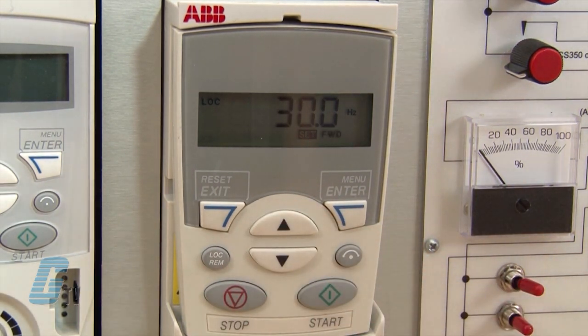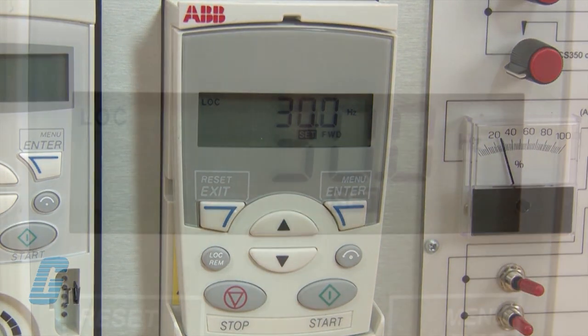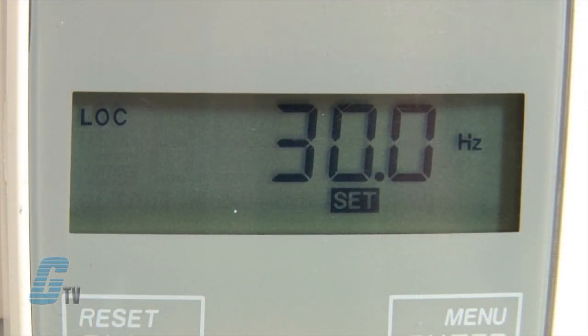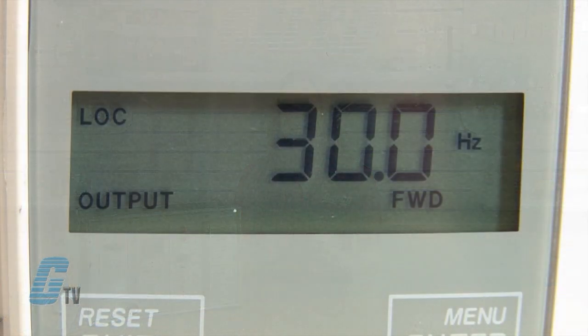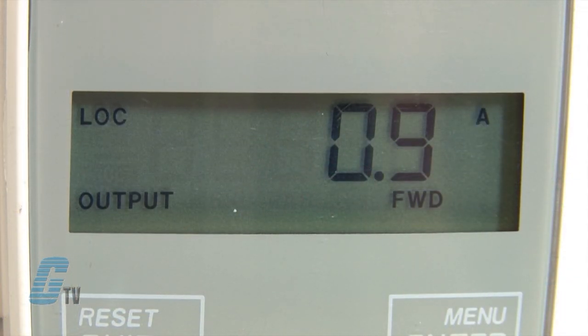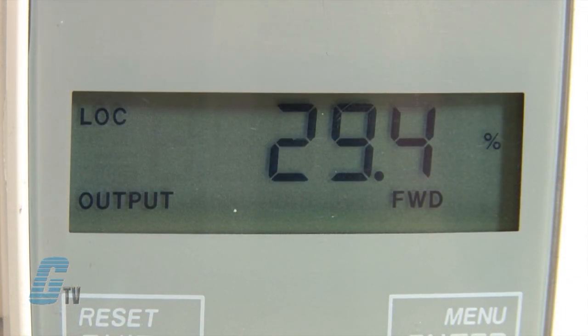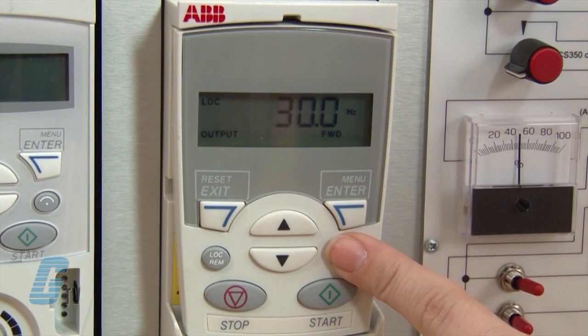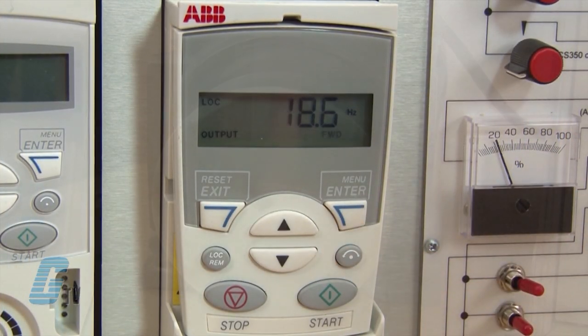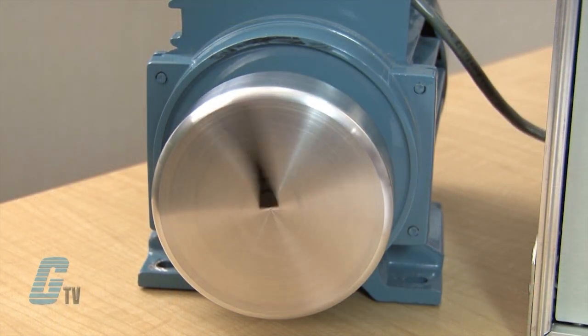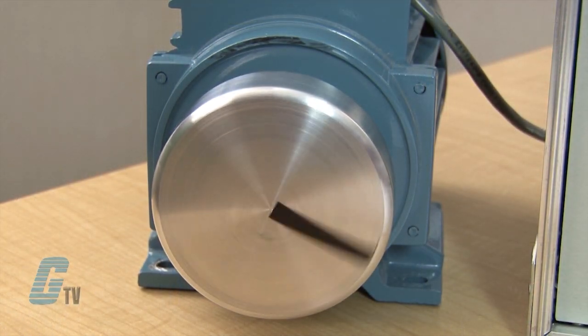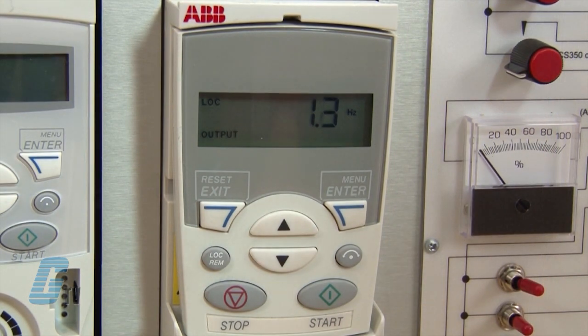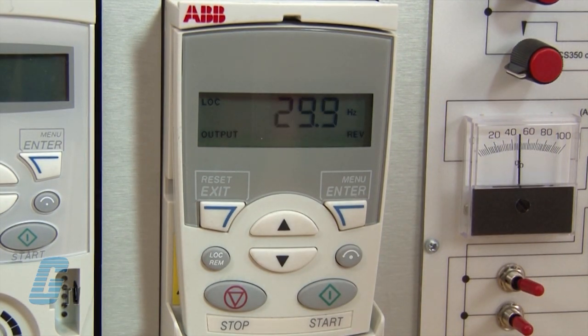I can now push the up arrow for my desired speed and then push the start button. The bottom should flash forward until it reaches the set point. Once the desired speed is achieved, the forward indicator will turn into a steady on. By pushing on the arrow keys in the output screen, I can check the speed, current drawn, and the percentage of torque the motor is producing. I can push the direction button to switch the direction of the motor. The drive will ramp the motor down to zero speed and reverse the motor direction. The bottom right will display reverse and the motor will then ramp back up to the commanded speed.